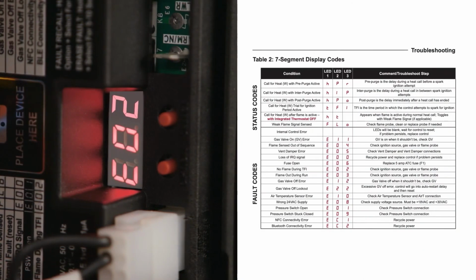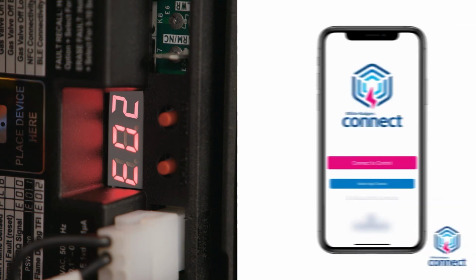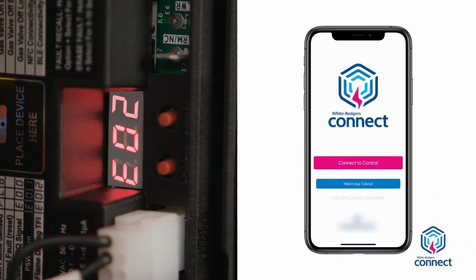The 3 digital LEDs convey system status and active fault codes. If any errors occur during a cycle, a fault code will indicate the error. For an active error condition, the LEDs will display an E followed by 2 numbers. The module is displaying error E02. The fault code label indicates no flame during a trial for ignition. Up to 5 fault codes can be stored in the sequence they occurred. Fault code errors can be recalled through the White-Rodgers Connect mobile app.